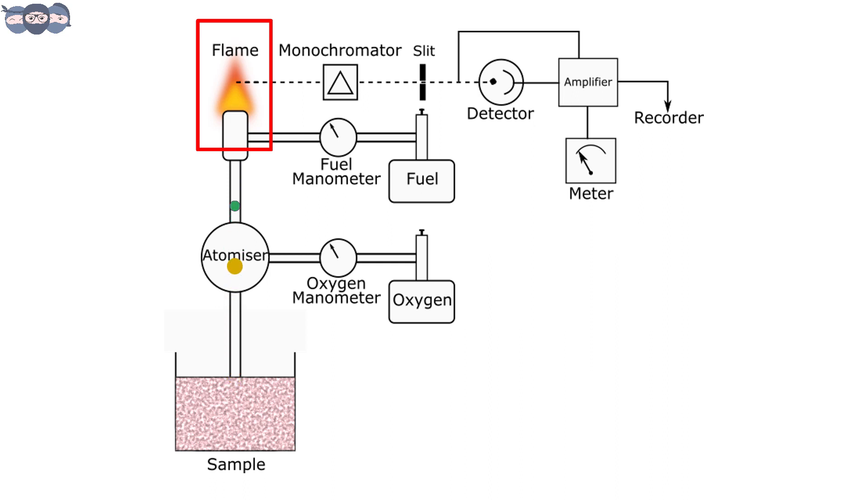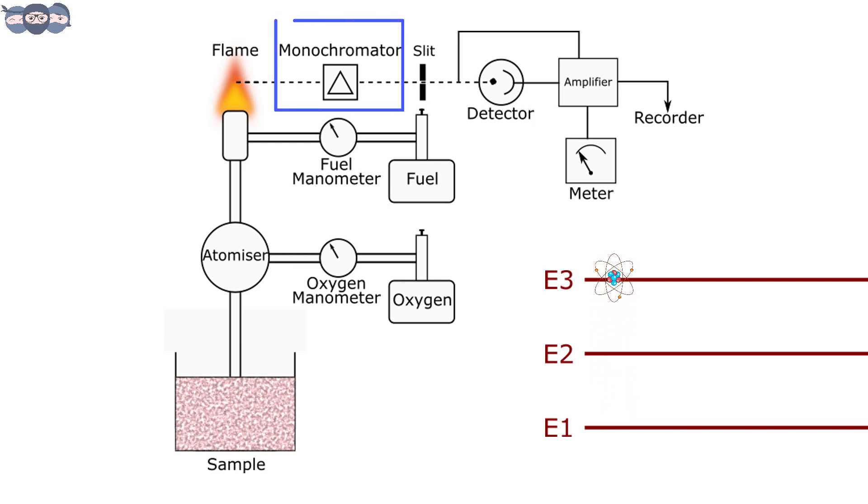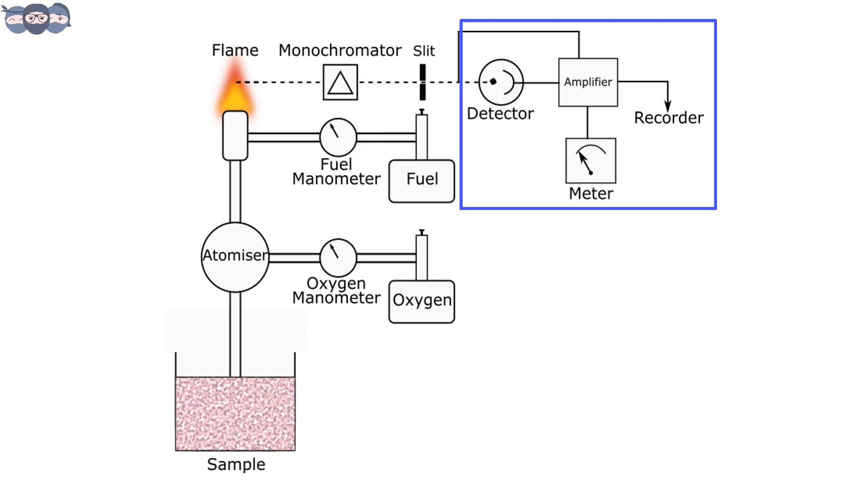The next component is the flame. The flame is employed to heat the aerosolized sample and provide energy to the atoms present in the sample. The atoms take up this energy and go to higher atomic state. The flame is followed by a monochromator which filters out the wavelengths, and the final part of the instrument is the detector and display.